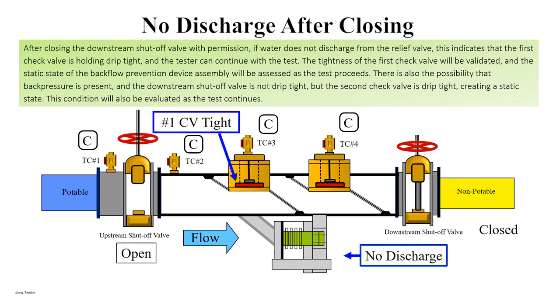No discharge after closing. After closing the downstream shutoff valve with permission, if water does not discharge from the relief valve, this indicates that the first check valve is holding drip tight and the tester can continue with the test. The tightness of the first check valve will be validated and the static state will be assessed as the test proceeds. There is also the possibility that back pressure is present and the downstream shutoff valve is not drip tight, but the second check valve is drip tight, creating a static state. This condition will also be evaluated as the test continues.